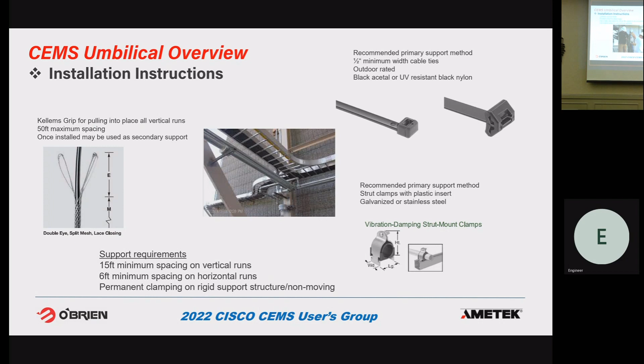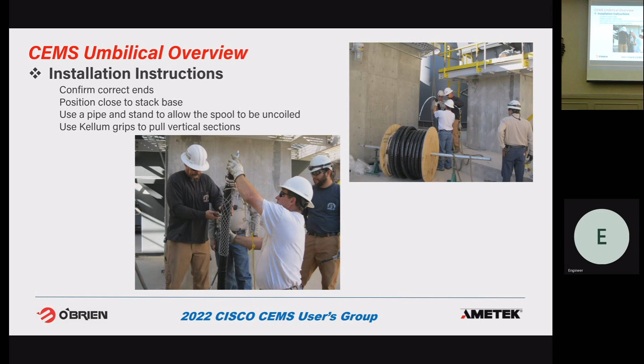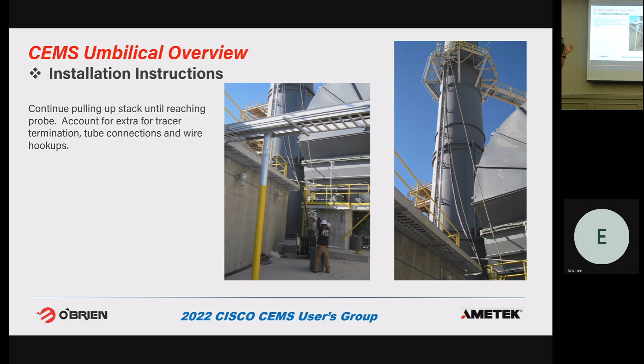This shows one of the installs I went on. They're putting their first Kellum grip on. They've got the bundle here with a pipe through it, lifted up off the ground, and a rope going up to the top off of a pulley. These are kind of dark, but they're starting to pull it up the stack here, and at least no more than every 50 feet they're stopping, putting another Kellum grip on, attaching it to that rope, and pulling it up the stack.